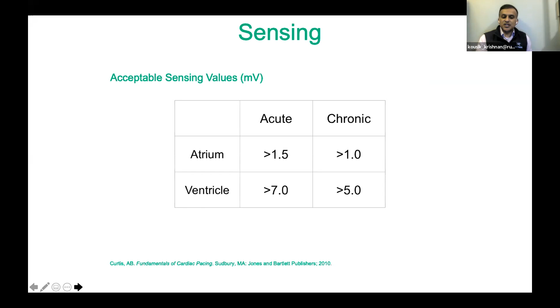In the atrium, sometimes that does also still play a role because depending on where you place the lead, you may sense far field signals from the ventricle that you want to filter out as well. But in general, we want to see at least 1 or 1.5 millivolt signals in the atrium and 5 or more millivolts in the ventricle in order to allow us to set the sensitivity to take out other signals that we don't want to see.